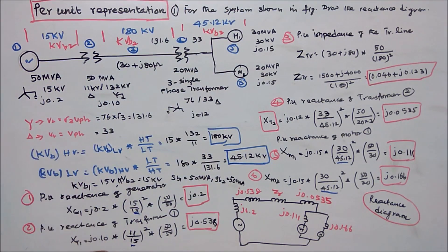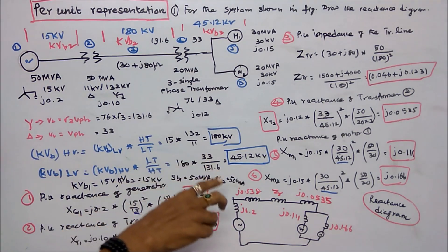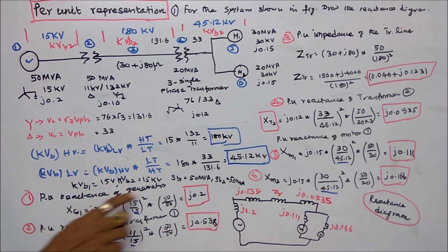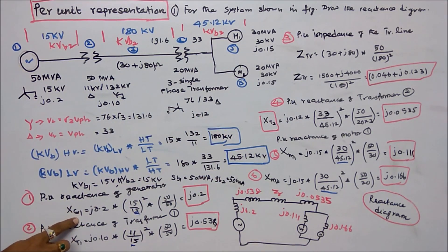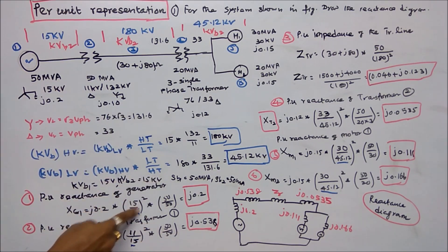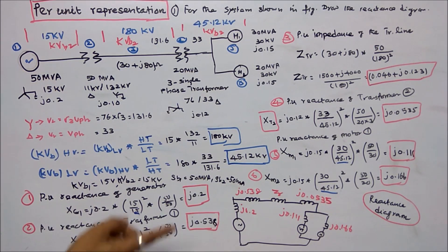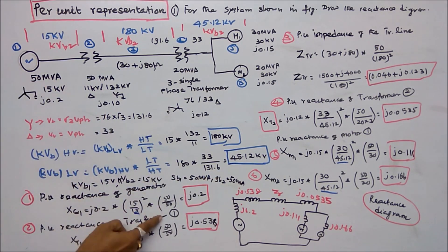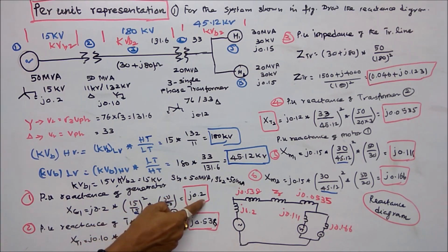Chosen value is 15 kV and SB2 is 50 MVA. First, find the per unit reactance of the generator. XG1 equals actual given reactance J0.2 into (VB1/VB2) squared, which is (15/15) squared, times SB2/SB1, which is 50/50. That equals J0.2 per unit.